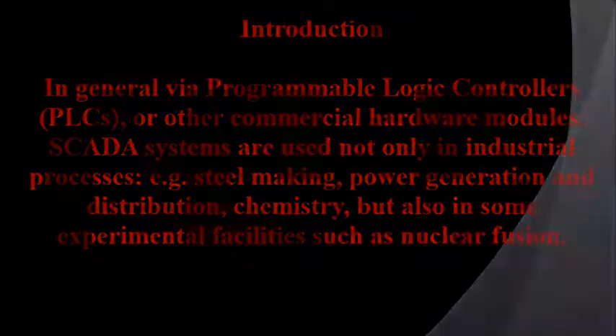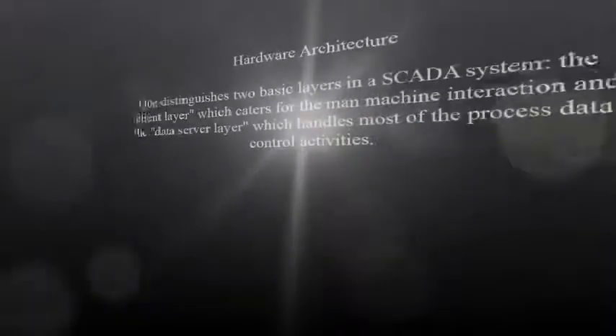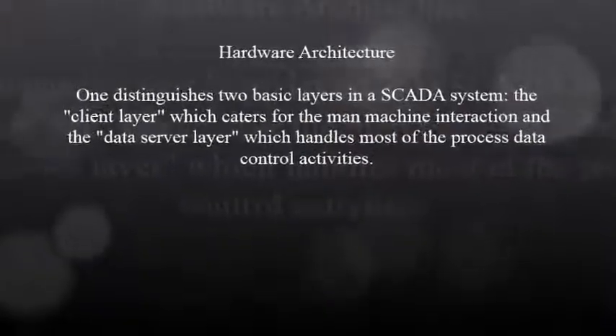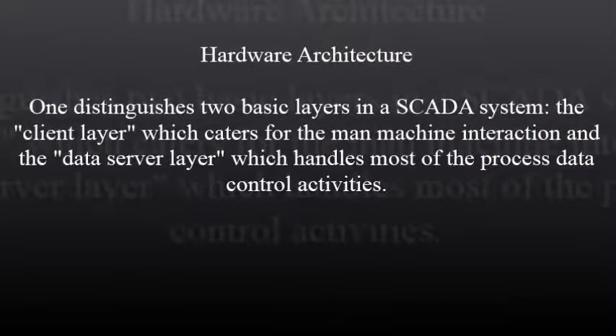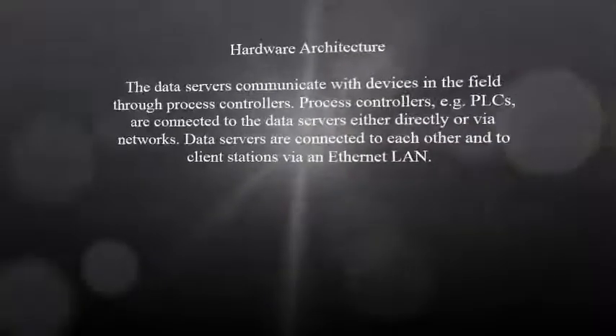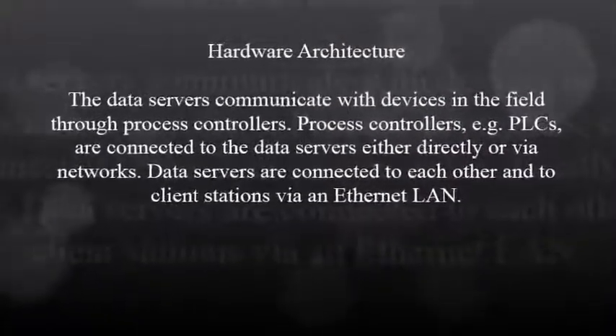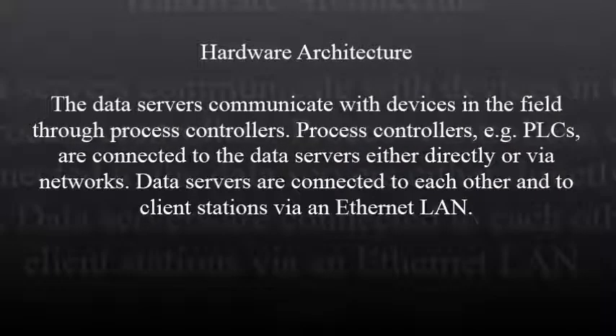Hardware Architecture. One distinguishes two basic layers in a SCADA system: the client layer, which caters for the man-machine interaction, and the data server layer, which handles most of the process data control activities. The data servers communicate with devices in the field through process controllers — for example PLCs — connected to the data servers either directly or via networks. Data servers are connected to each other and to client stations via an Ethernet LAN.